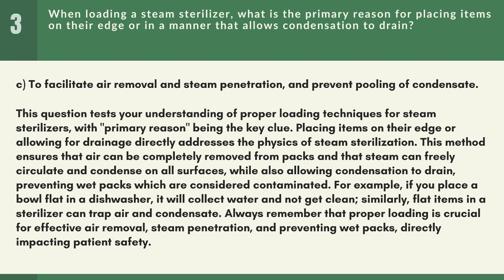Answer: C. To facilitate air removal and steam penetration, and prevent pooling of condensate. This question tests your understanding of proper loading techniques for steam sterilizers, with primary reason being the key clue. Placing items on their edge or allowing for drainage directly addresses the physics of steam sterilization. This method ensures that air can be completely removed from packs and that steam can freely circulate and condense on all surfaces, while also allowing condensation to drain, preventing wet packs which are considered contaminated.